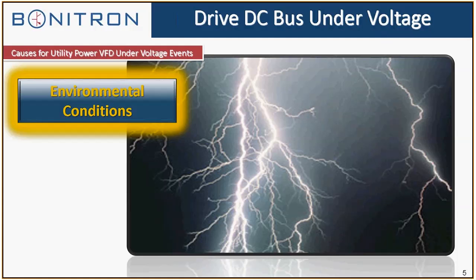Now, just backing up a little bit, as we know, ride-through is usually specified due to utility power events. Every region is going to be different, and by the time we get to the point where the customer has decided what ride-through, along with help from you guys out there and the Bonitron technicians back here, it's going to vary from region to region, of course. Usually in the United States we deal with sags, but there are some specific outage requirements. Usually we categorize the UPD products into short-term outage, long-term outage, and sag ride-through.